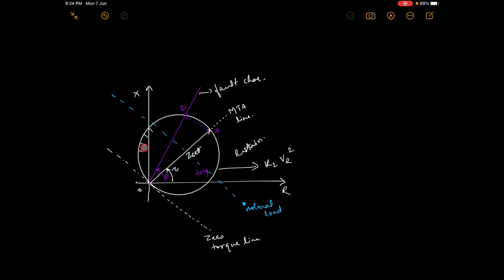So since the radius, or the circle, is very small, it doesn't engulf the normal load condition. So here it will not operate. You can see that outside this circle there is no operation, that is, no tripping. Fine. It comes under restraint, so it will not consider the normal load as the tripping region.